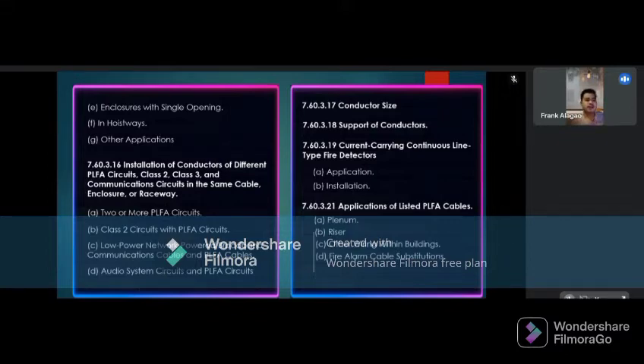Conductors of one or more Class 2 circuits shall be permitted within the same cable, enclosure or raceway with conductors of power limited fire alarm circuits, provided that the insulation of the Class 2 circuit conductors in the cable. Letter C is power network powered by broadband communication cables or PLFA. So low power network powered broadband communication circuit shall be permitted in the same enclosure or raceway with PLFA cables.